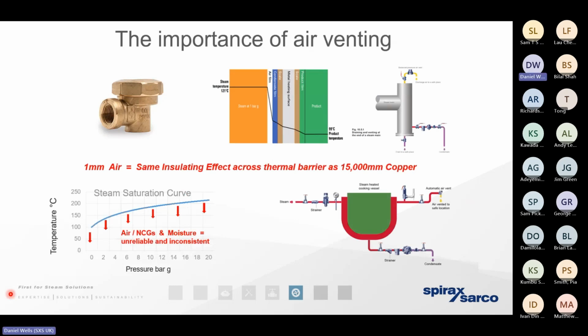Other things that we want to give thought to: we want to get the air away from the steam system. Now, we always treat the water in the boiler, but that's primarily to protect the boiler itself from the result of oxygen corrosion or oxygen pitting. We can never guarantee that we're getting oxygen and other non-condensable gases out of the steam system. And that's because when a steam system's switched off, the steam condenses, and therefore it pulls a vacuum. So it could be pulling air in from valve spindles, gaskets, vacuum breakers, for example. It's important that we get that air away, because if that air is left in the infrastructure, that can be the number one cause of corrosion that we experience.